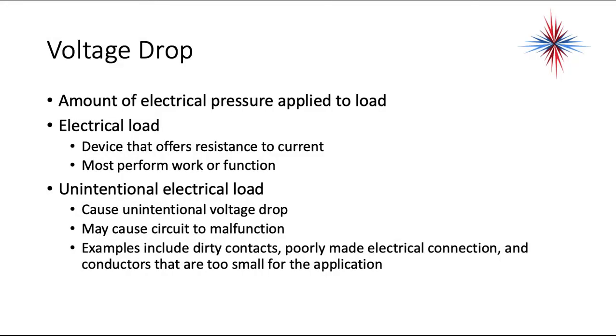Voltage drop is the amount of electrical pressure applied to a load. An electrical load is a device that offers resistance to current, and it must perform work or a function. Unintentional electrical loads can cause unintentional voltage drop, and they can cause circuits to malfunction. Examples of unintentional electrical loads could be dirty contacts, poorly made electrical connections, and conductors that are too small for the application.